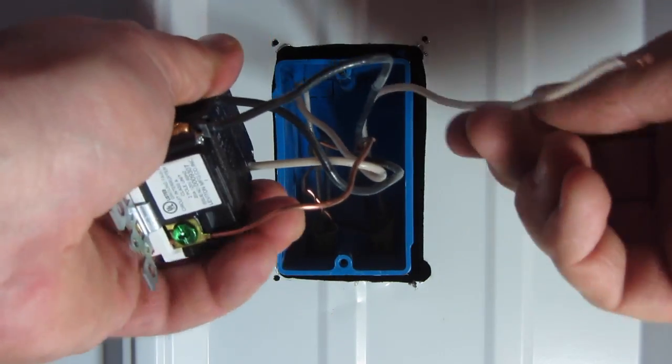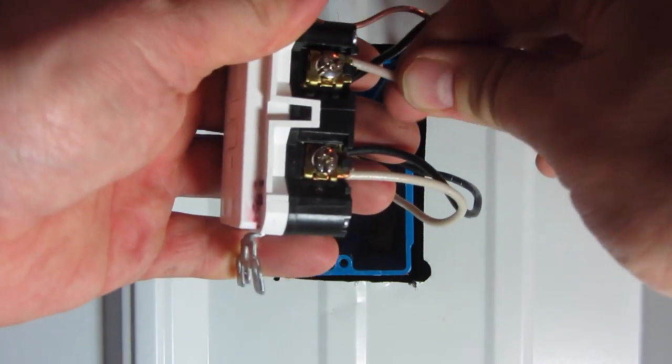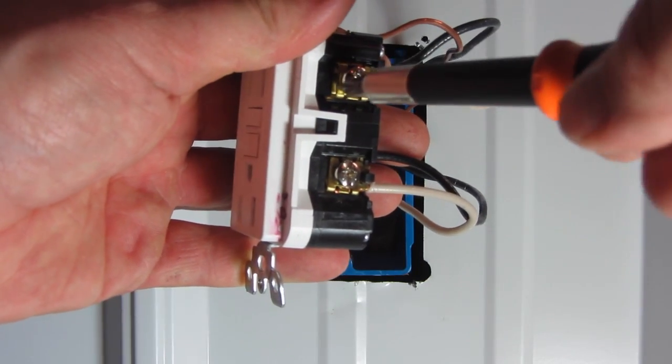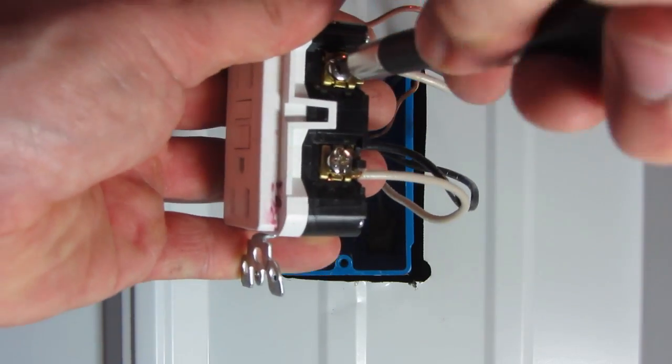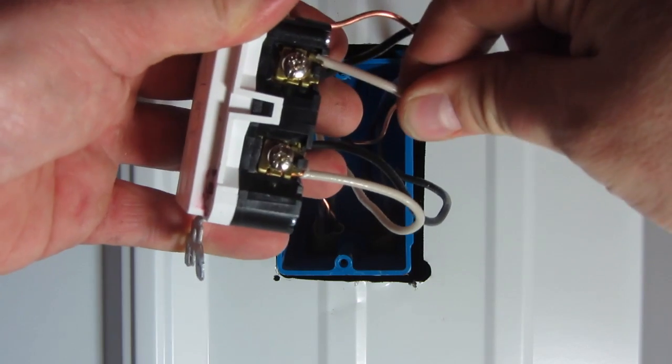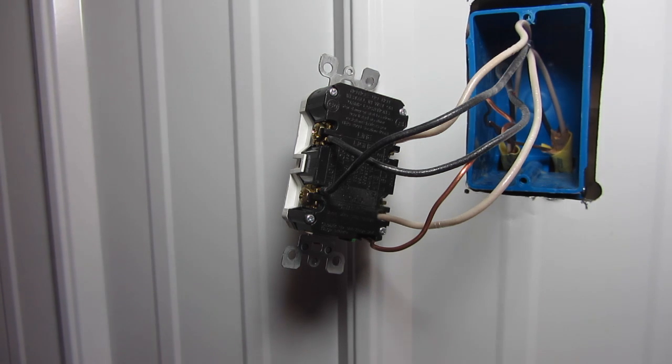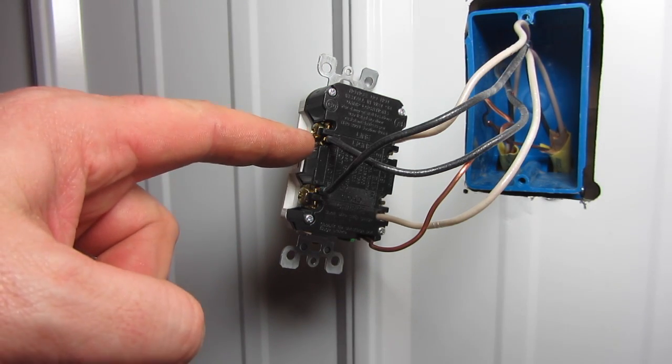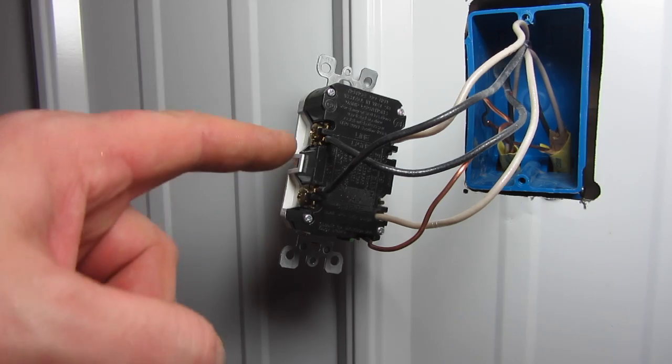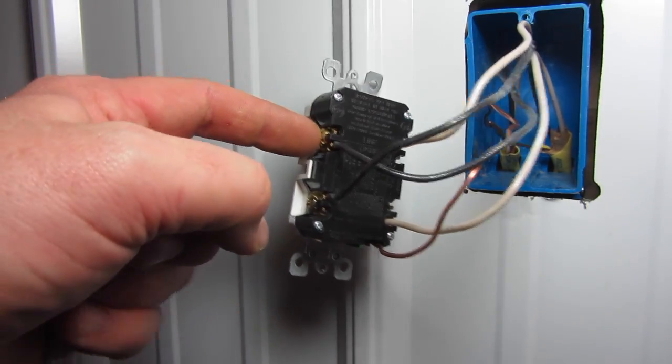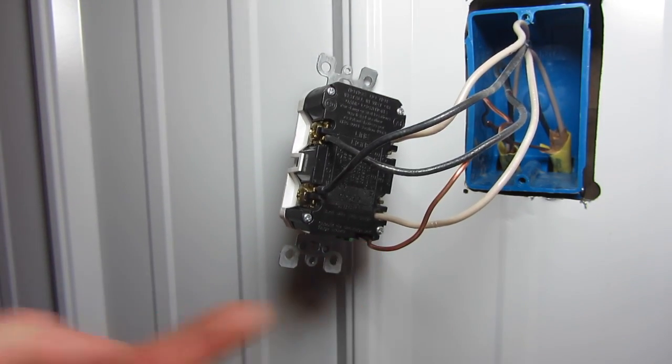Then I take the white to the silver. Once you feel the terminal screws are tight enough, go ahead and double check to make sure the line is going to the line and the load is going to the load side. Also, double check to make sure the black is going to the gold screws and the white is going to the silver screws. Also, check the tightness on your ground as well.